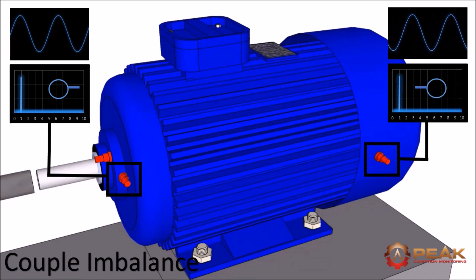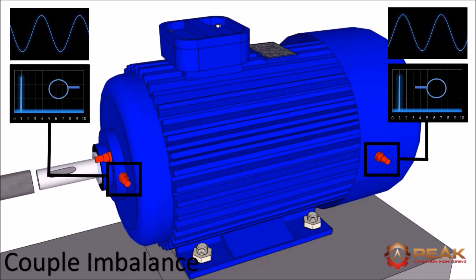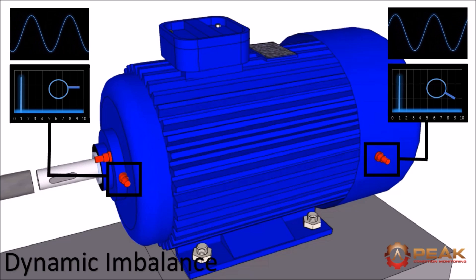A couple imbalance would show the two waveforms to be 180 degrees out as shown here. Finally a dynamic imbalance would show the vibration to be out by any other angle, neither completely in or out of phase.